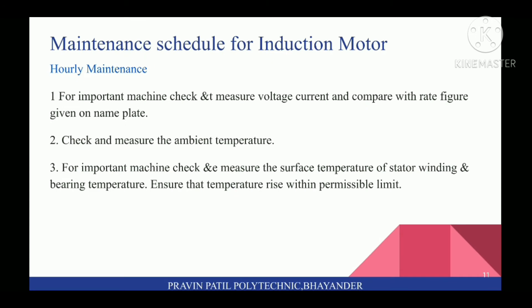Next topic is Maintenance Schedule for Induction Motor. On Hourly Maintenance: first, for important machines, check and measure voltage and current and compare with rated figures given on the nameplate. Second, check and measure the ambient temperature. Third, check and measure the surface temperature of stator winding and bearing temperature. Ensure that temperature rise is within permissible limits.